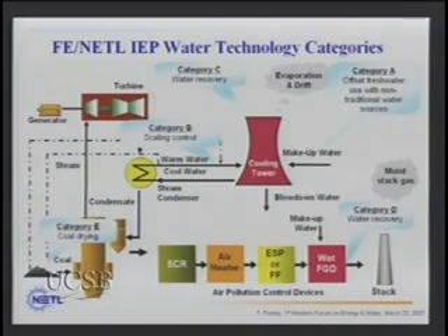And this moved kind of quickly, but what I wanted to point out is that the primary places of water loss in a power plant are out the cooling tower stack. That's the major consumptive loss. But you also have loss out of the stack gases, or from the flue gas. And you also have blowdown, depending on the cycles of concentration you have around your cooling system. But the major loss is evaporative loss out of your cooling tower.